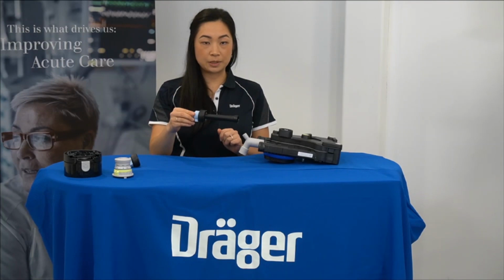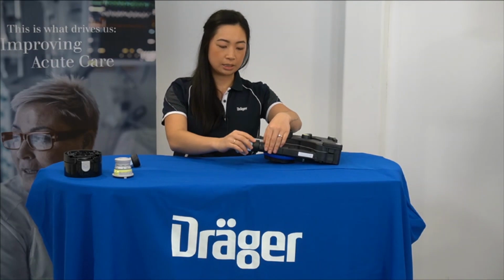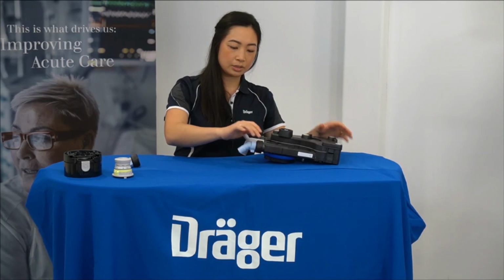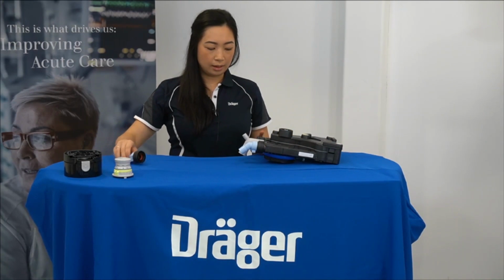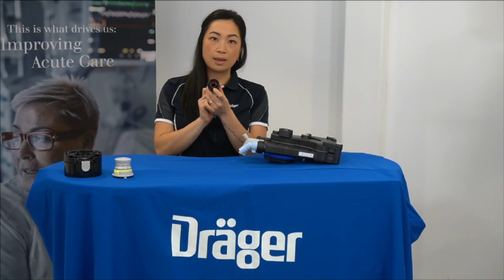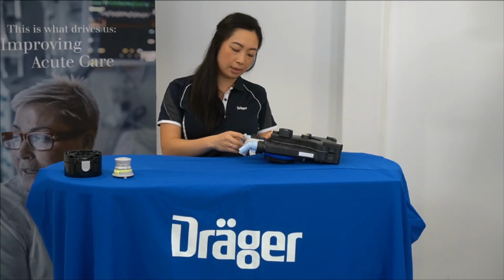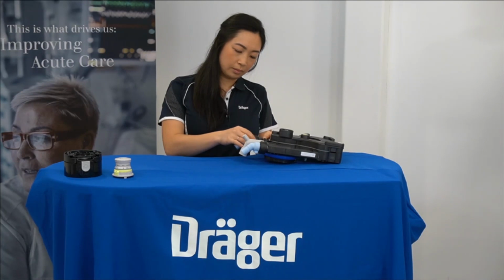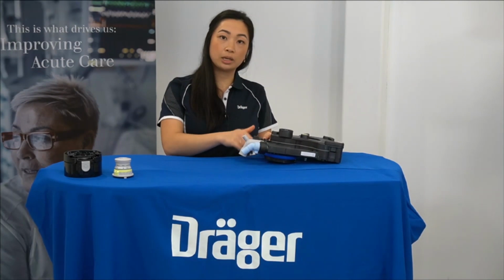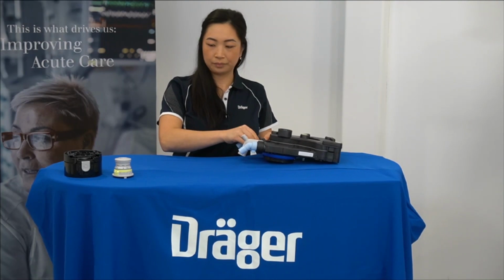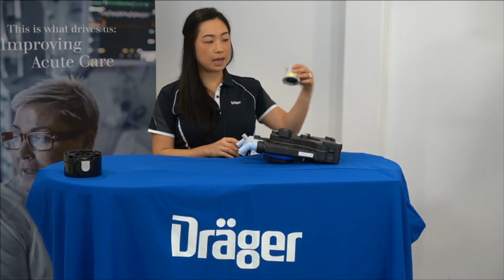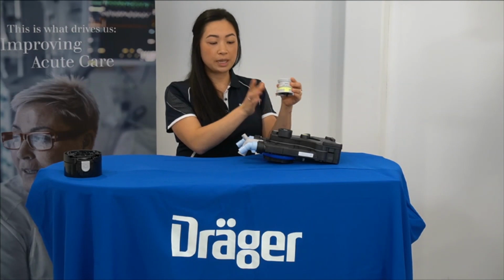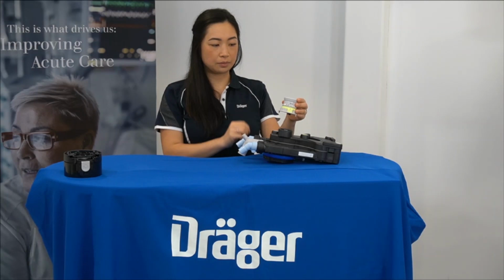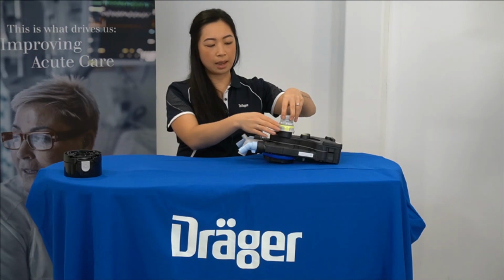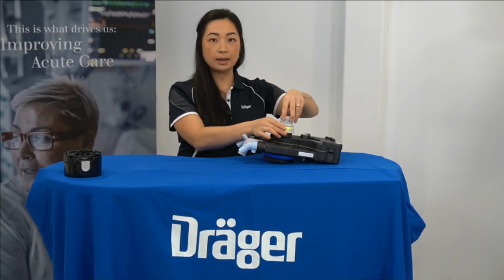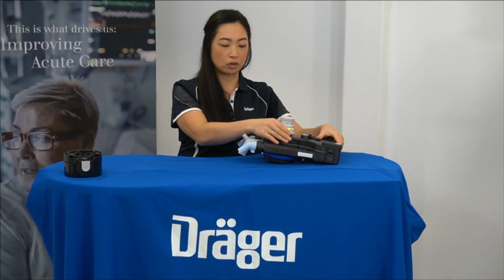Then, the expiratory port inserted here and screwed on, and the inspiratory one to the top. And just keep in mind there is a notch at the bottom that aligns with the gap at the edge of the port. And just screwing it on so that it's finger tight. Next, reattaching the APL valve. The dot should be aimed to the front of the breathing system, with one hand supporting where that APL valve should sit, and with the other hand screwing the base of the APL valve onto the cover.